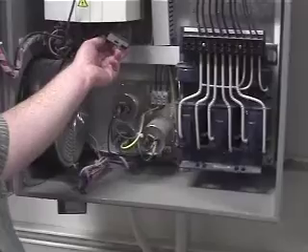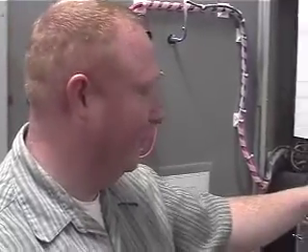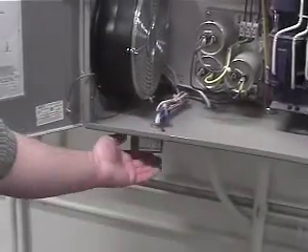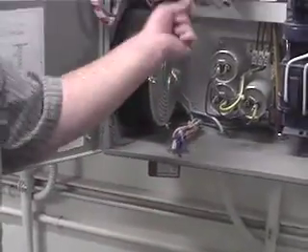This one right here is a transducer, so what we're doing is, because that pump is on or off, it's a constant speed, so it's generally the same amount of current draw. This one right here, since it ramps up and down, we want to know what the different current is. I just wanted to point out all the VFDs, so all your pumps, air handlers, all use an analog transducer to measure the current, not a switch. And the reason I pointed that out is because this right here is your command, because it's not a combo relay. If that makes sense.